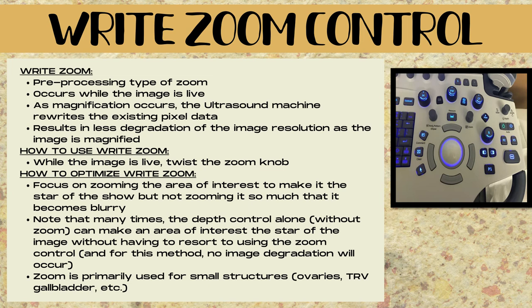Write zoom occurs while the image is live, and as the magnification occurs, the ultrasound machine is rewriting the existing pixel data. This results in less degradation of image resolution as the image is magnified. To use write zoom, you twist the zoom knob while the image is live, magnifying the image as you scan.